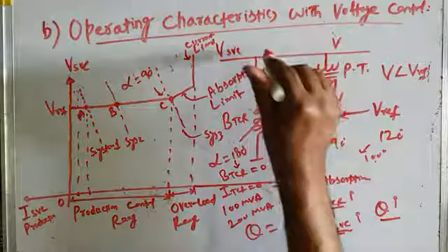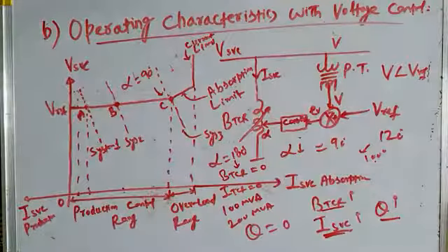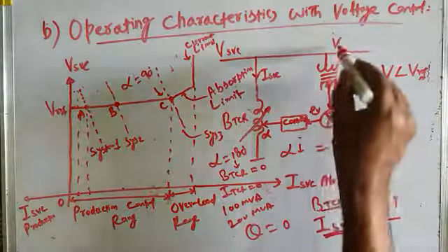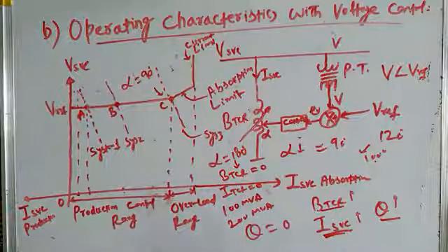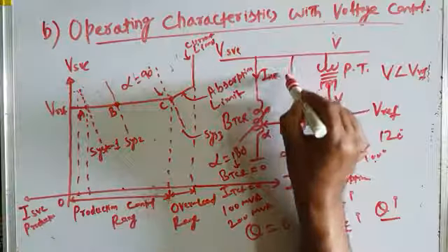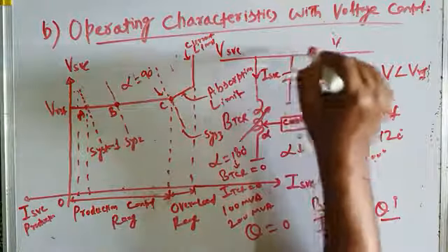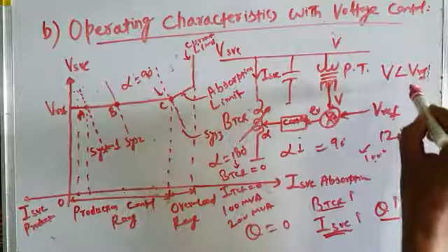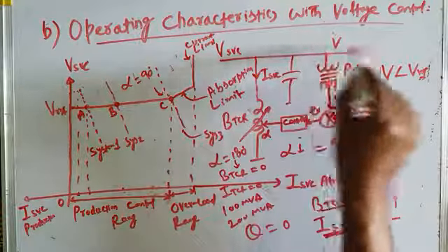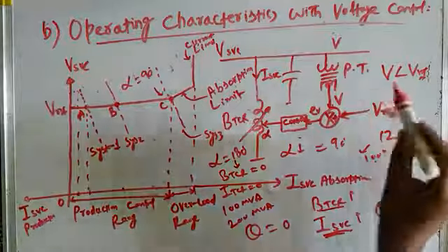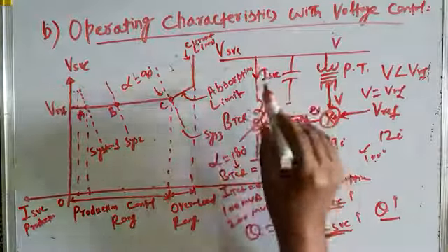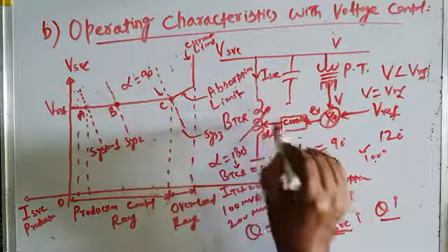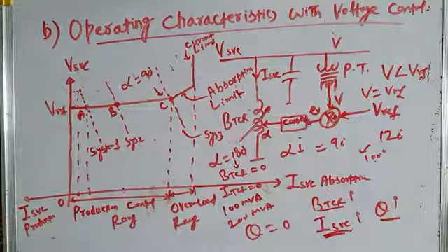Now positive reactive power, or lagging VARs, are flowing on the line, and those lagging VARs are making V less than Vref. To compensate for them, you need to connect a capacitor bank which will inject the reactive power required by the load, and it will make V equal to Vref. In that case you may not require the TCR to absorb any reactive power.